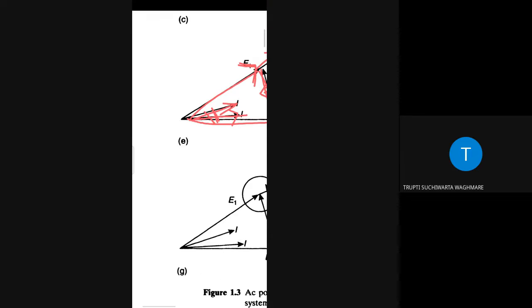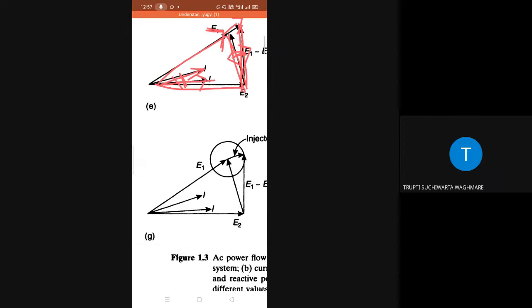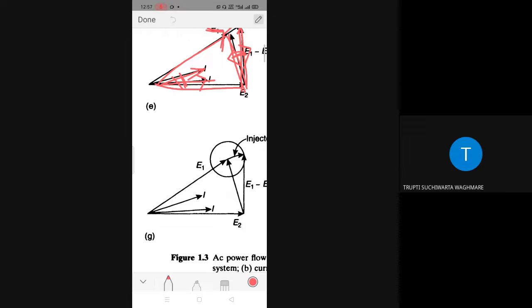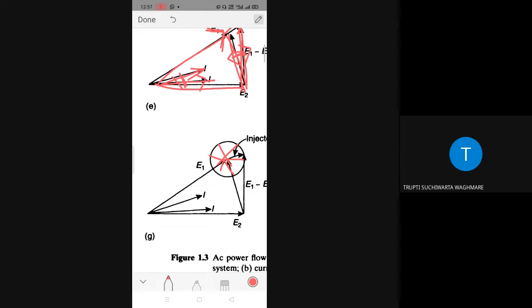And obviously in between, suppose I inject the voltage such that I am able to make it either in phase with the end voltage or in phase with the driving voltage. If I can control any phase relationship, it means I can connect one voltage source in series with the transmission line. By means of that, I am injecting the voltage at any phase angle, 360 degrees. That may be in phase with the end voltage, in phase with the voltage drop across the transmission line, or any other phase angle. According to that, I will control the magnitude of current and the phase angle of current flowing through the line, and accordingly I am able to control both real and reactive power flow through the transmission line.